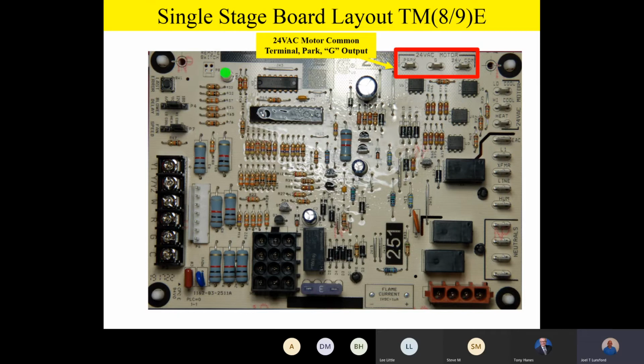Now put your thinking cap on for a second. On a regular PSC or permanent split capacitor type of motor, if you commanded more than one speed command on that motor at the same time, you'd burn the thing up, right? So one of the things that I really, really like about high efficiency ECM type motors is the fact that you can give it multiple speed commands and it will always go to the highest speed command that it's getting. So let me say that again. It's a 24 volt driven command. And if it has more than one 24 volt speed command on it, whether it's by way of a control board or a physical jumper like we have on this particular type of furnace or control board, if it has more than one speed command, it will always go to the highest speed command that it's getting. We call that airflow priority.